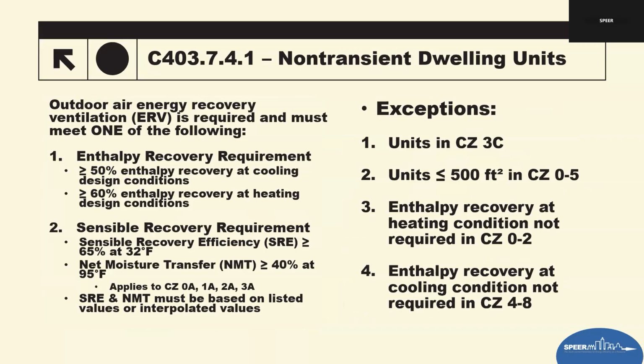Non-transient dwelling units, so new energy recovery requirements for these units in commercial buildings that function like permanent residences, such as apartments, dorms, assisted livings, or extended stay facilities. The 2024 code requires that these units use outdoor air energy recovery unless they fall under specific exceptions. This refers to the process of capturing both sensible and latent heat from the exhaust and transferring it into the incoming air. So the main requirement is to provide an ERV. The code requires an ERV, an energy recovery ventilator, for all non-transient dwelling units. Again, this is what the book says. This may be different in your local jurisdiction.